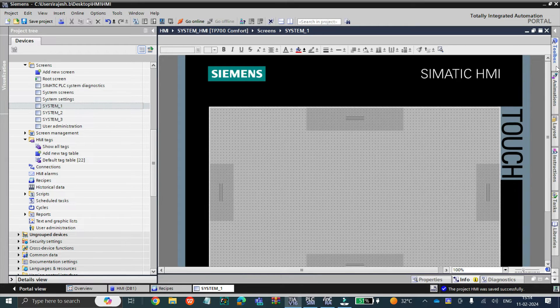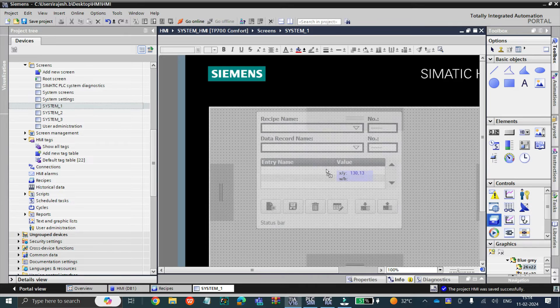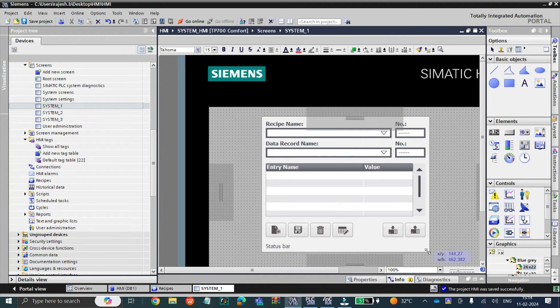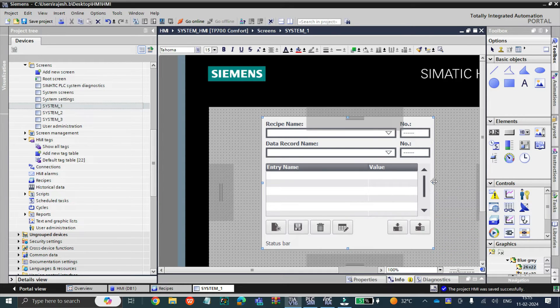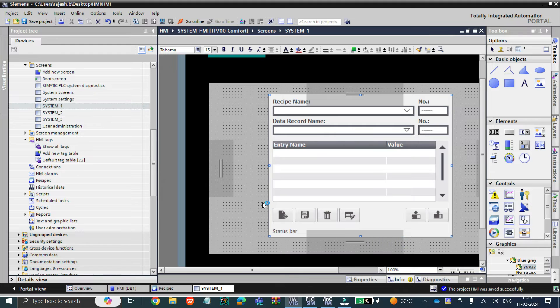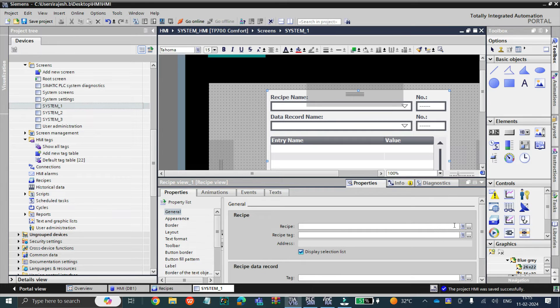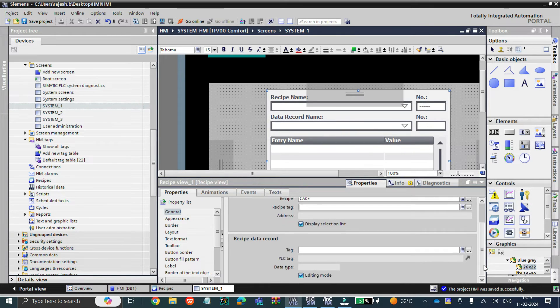I will take a screen — close the split view. In the toolbox on the right side, you can see there is an option called 'recipe'. This is the recipe view — you need to drag and drop it into your picture. In the property window, right-click on the recipe, go to the property, and in general select the recipe by clicking the menu. You can choose your recipe number or recipe — 'cake' is there with its data records. I don't want to assign the record tag right now, so let it be. I have chosen the recipe; now let's simulate.